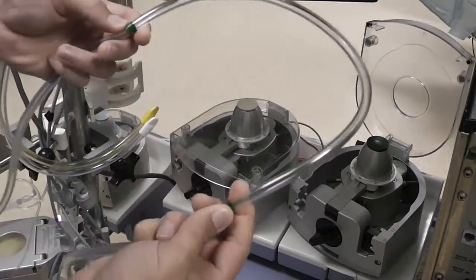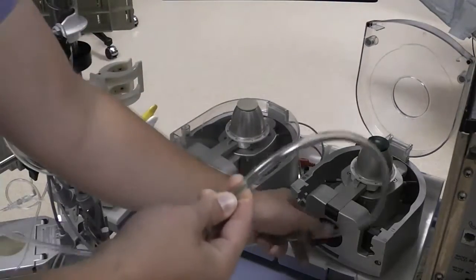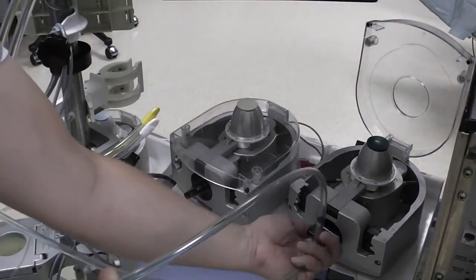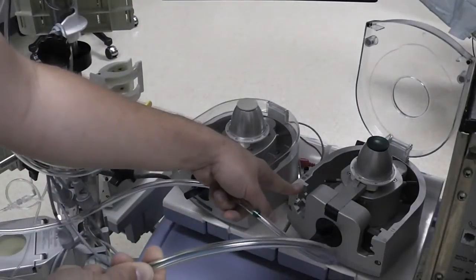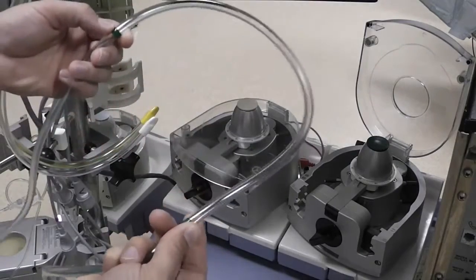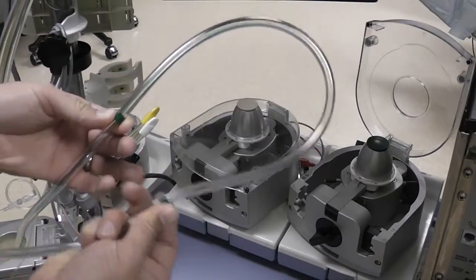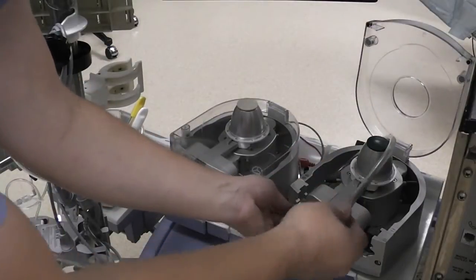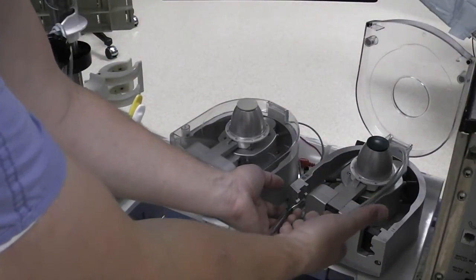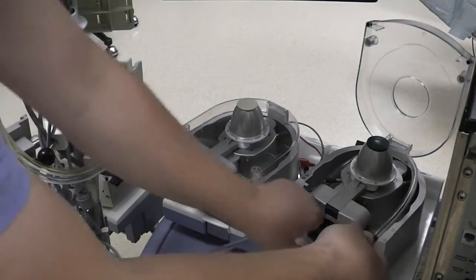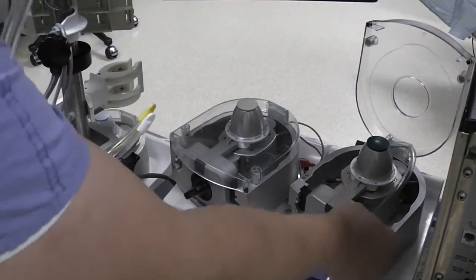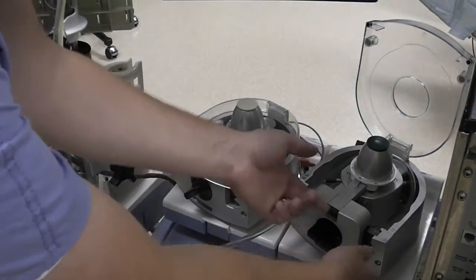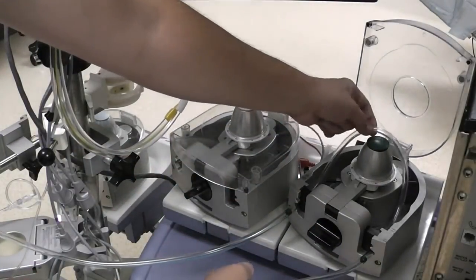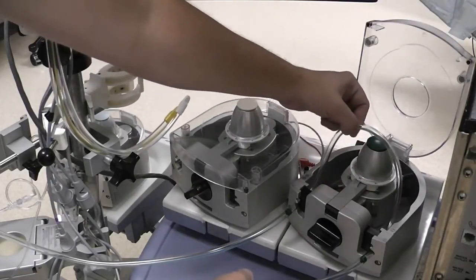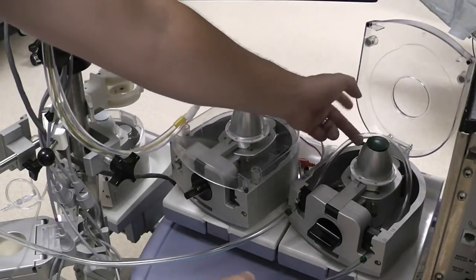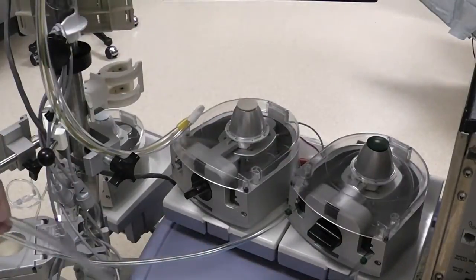and we're going to take our line. Let me start as if this is closed. We're going to rotate this so that the left side is open, and this has to go in the pump head between these two green tapes here. So we're going to put it down at the bottom of the pump head, pull this lever to close that connection, rotate the other side open, put that in, and close that. So you'll see this line is hanging above the back of the roller here, and that's how we set the pumps up. Then you just close the lid on top of that.